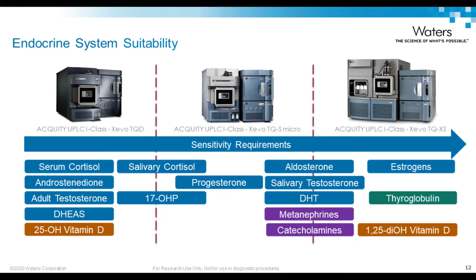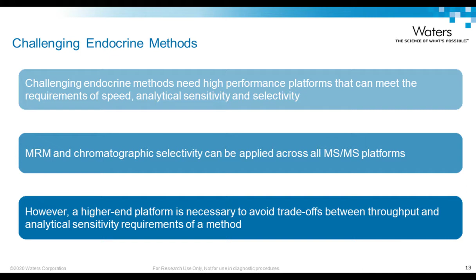In order to meet the demands of more challenging applications, higher performance LC-MS platforms are needed to meet the requirements of speed, analytical sensitivity, and selectivity. MRM and chromatographic selectivity can be applied in the same manner across all the Acquity UPLC Xevo mass spectrometer systems. However, a high-end platform such as the Xevo TQS Micro and Xevo TQ XS are necessary to avoid the trade-offs between sample throughput or speed and analytical sensitivity requirements of a method. Now I would like to cover examples of applications where we are striving for either analytical sensitivity or speed while maintaining selectivity of the methodology using LC-MS.